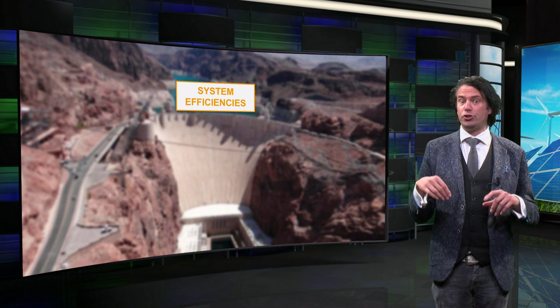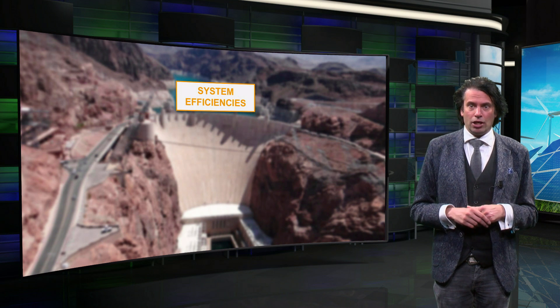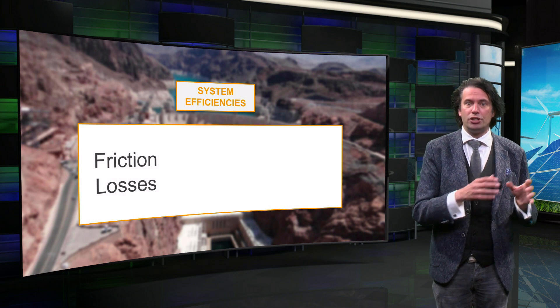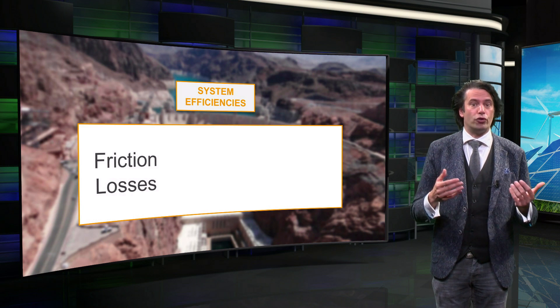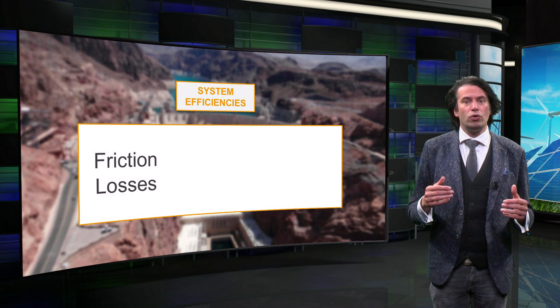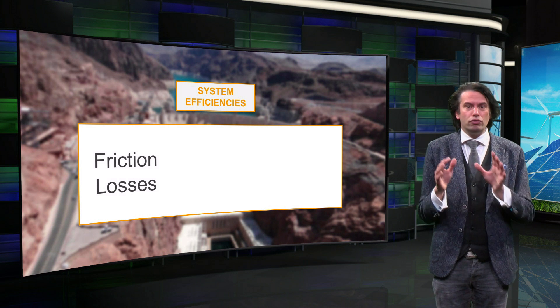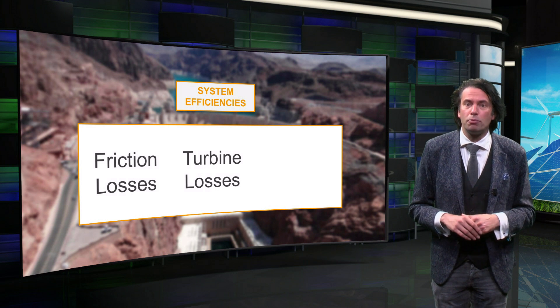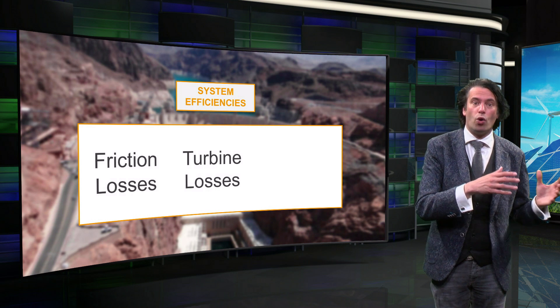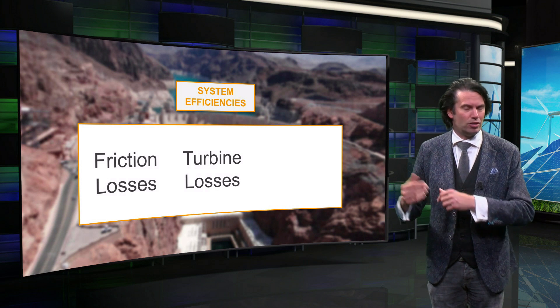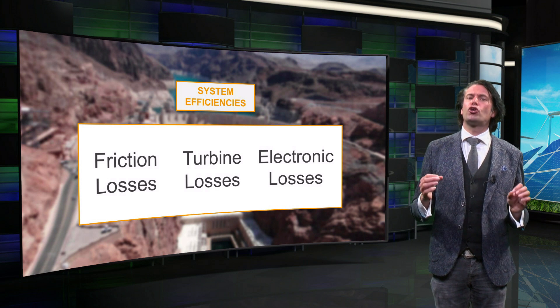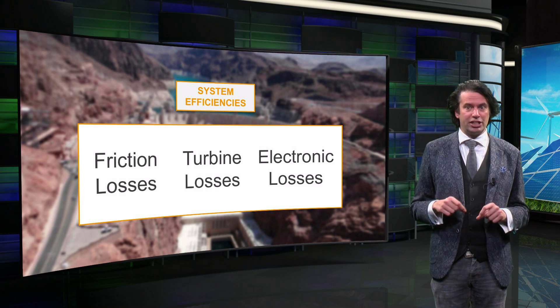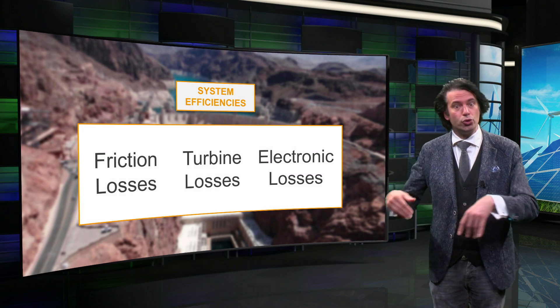There are some factors that reduce the conversion efficiency of a hydro plant. The losses in the hydropower system are mainly caused by three factors. When the water flows from the inlet to the outlet, the potential energy is converted into kinetic energy. The water flow loses some of its kinetic energy due to friction at the edges of the pipe. The second loss mechanism occurs when the turbine converts kinetic energy of the water to rotational or mechanical energy. Finally, some losses occur in the generator and transformer, where mechanical energy is converted to electric energy and when the electrical energy is converted to a higher voltage.